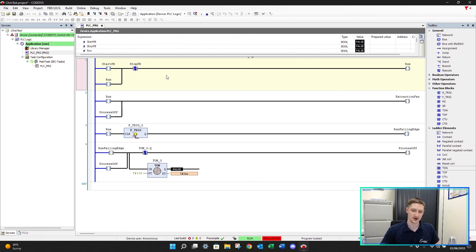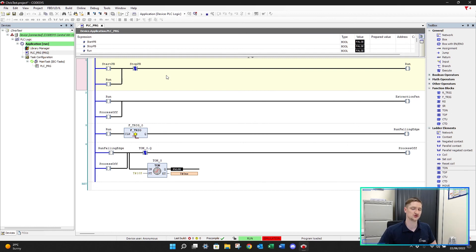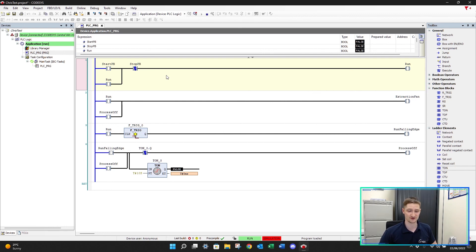So if you don't have the off delay timer, that's how we can create it. We need the F_TRIG first of all just to detect that falling edge, and then we can use a standard on delay timer to create it. Every timer other PLCs give you - your off delay timers - you can create all of these with just the on delay timer. So if you don't have it, create it; don't worry about not having that timer available to you.